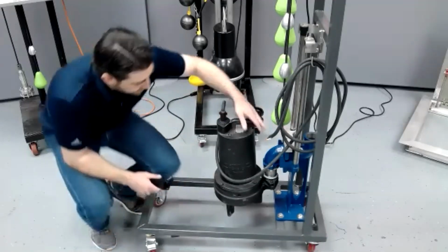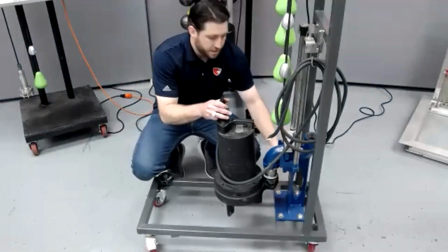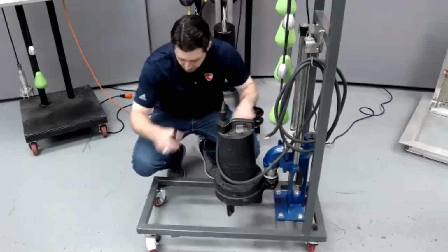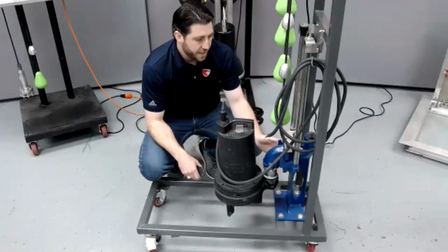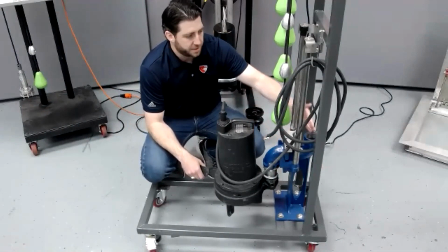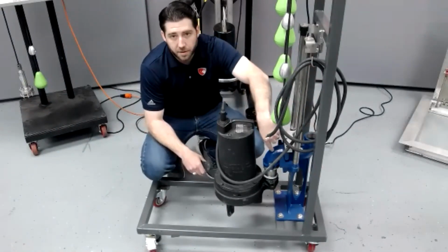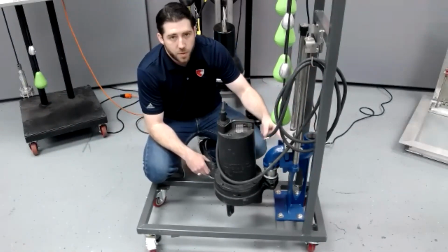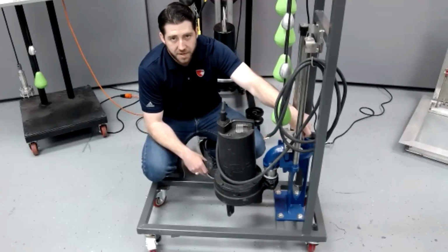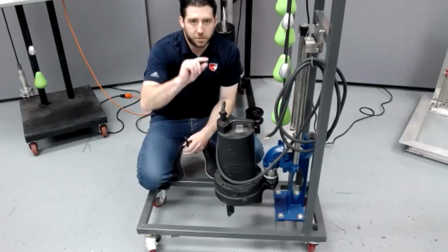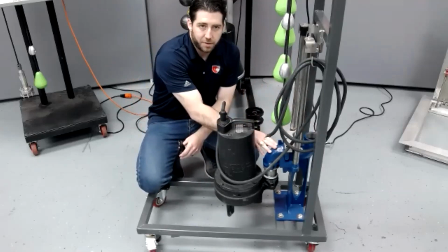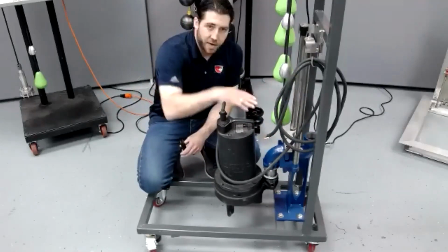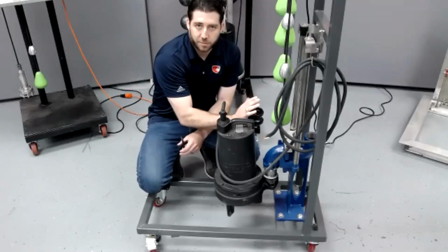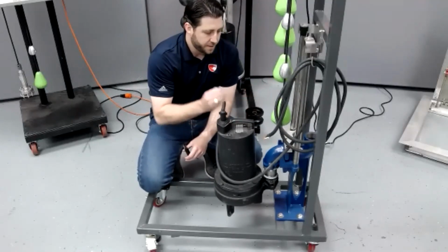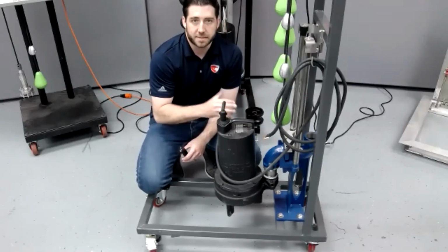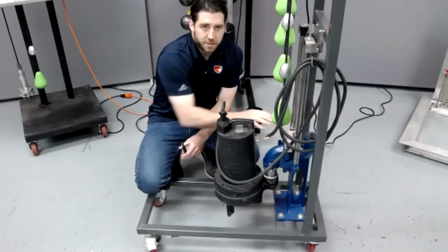So we have the base elbow here, which is permanently installed. This piece here, you can see my hand, is what's going to be installed on the base of the pit, and is what our discharge piping is connected to. Connected to the pump is this slide rail adapter, and that's going to connect the pump to the discharge piping on the base elbow. There's a little O-ring or rubber gasket built into the slide rail adapter that helps create that seal. And the weight of the pump sitting on it is typically what will seal it in place. We've tested some of these with air, and they'll hold up to as much as 40 or 60 psi. So you can get a very good seal with this type of application.